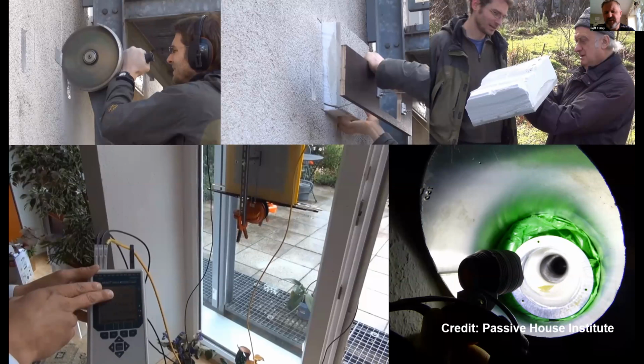I think they reckoned that one pane, one section of window where the U value wasn't right, they weren't sure whether it had lost its gas in the manufacture or over time. And the ductwork was checked as well. They'd never been cleaned and were clean as a whistle. Basically all of the components, including the MVHR system, which would have been a pretty primitive ventilation system, bar the electronics, the academic study predicted that all of these things would last at least another 25 years.